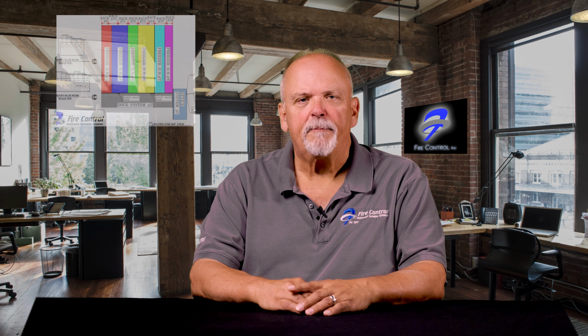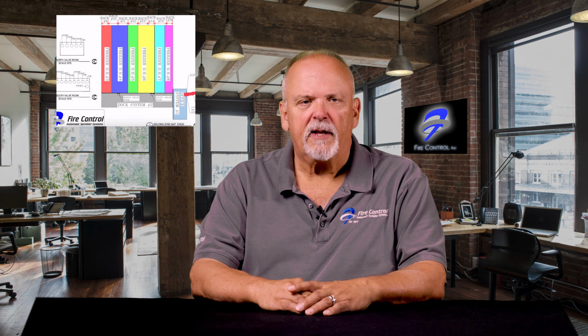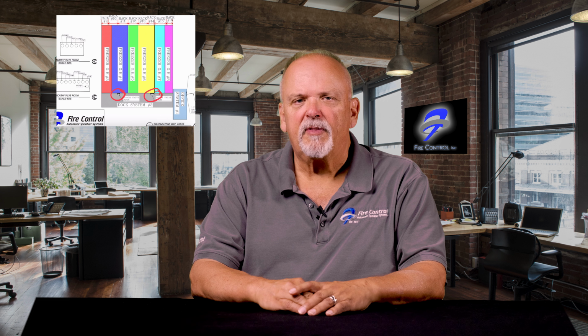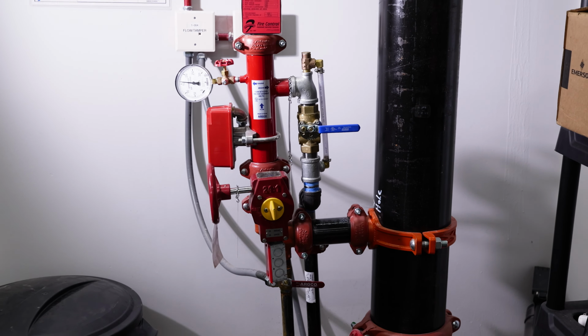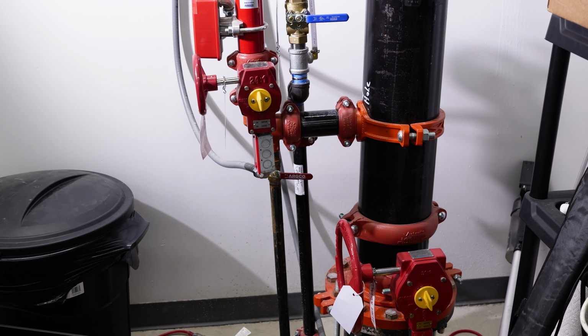At the bottom of the pump is a strainer screen and an anti-vortex plate to prevent air and debris from entering the pump. The sump is fed with water from the pond through a 12-inch concrete pipe and is fitted with dual debris screens at the entry to the pump. The fire pump is rated to adequately provide water to supply the various sprinkler systems in the building. It is piped underground to a point that enters the main building. Here, it transitions to an overhead feed main that supplies two valve rooms located on the shipping dock. In these rooms, systems are provided that protect the loading dock, the VNA and ASRS freezer rooms. Also located at the entrance to the water supply into the building is one wet pipe sprinkler riser that feeds sprinklers in the offices and maintenance areas.